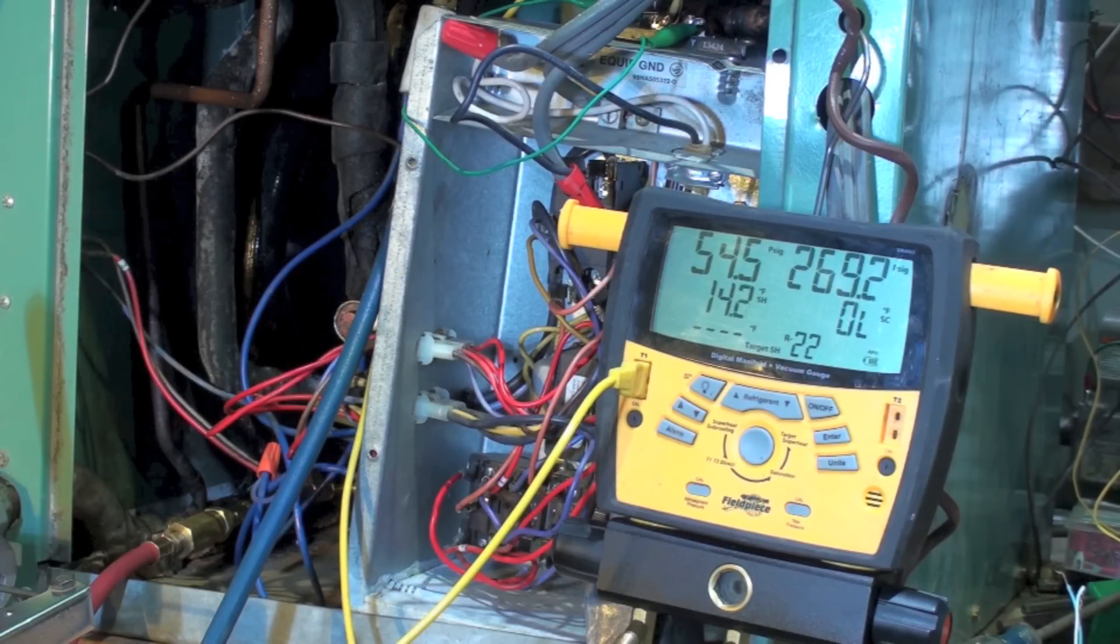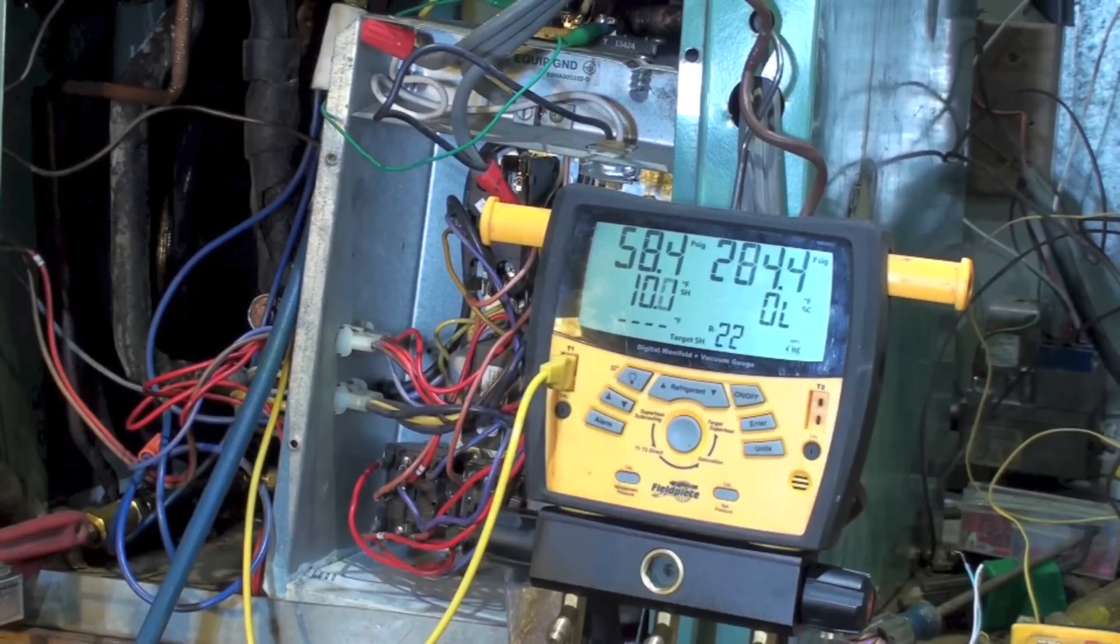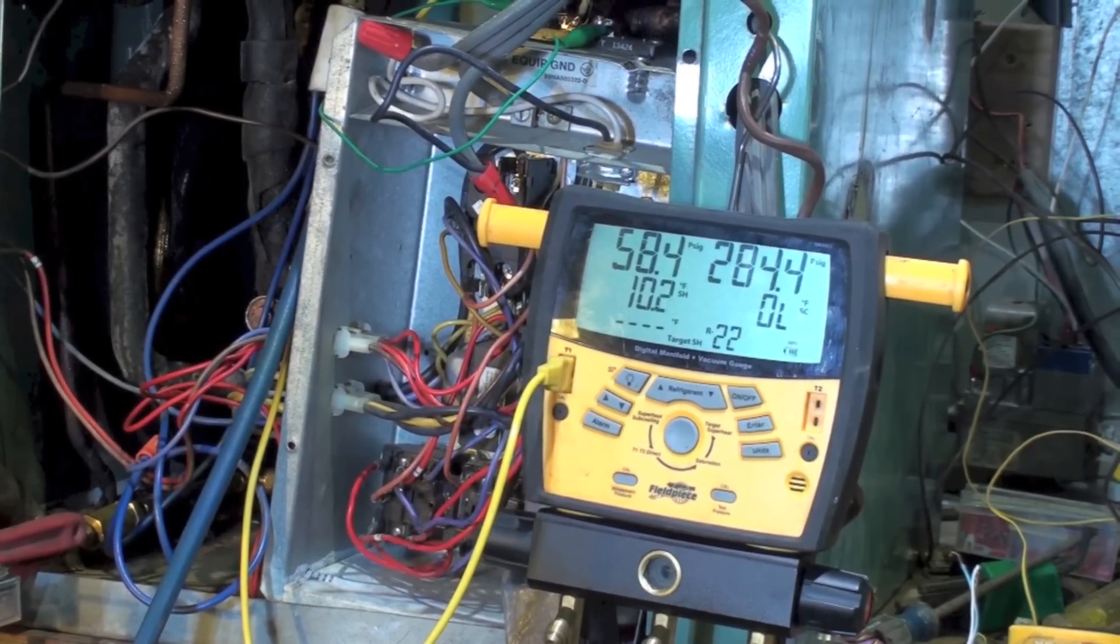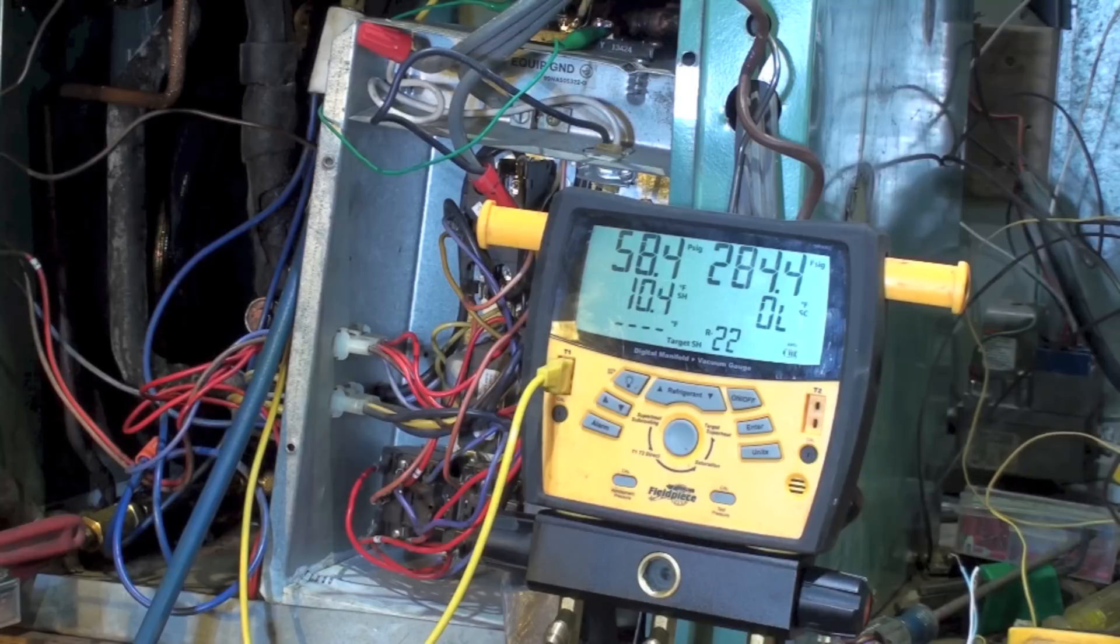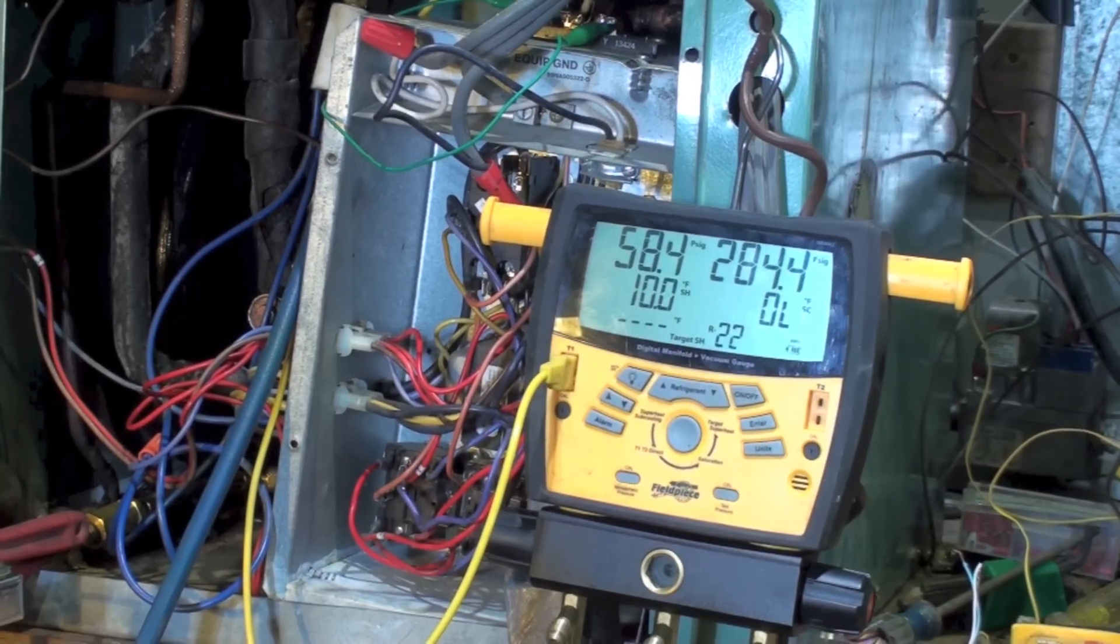54.4, 14.3 on the superheat, 269 on the head, and I don't have a liquid line temperature—this thing doesn't have a liquid line when it's in heat. Fiddled around a little bit with the charge and got this thing a little bit higher, maybe a little better suction pressure.